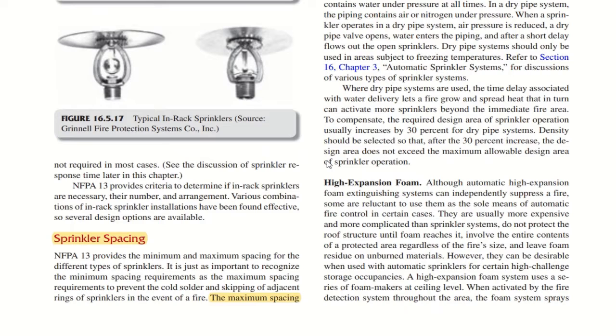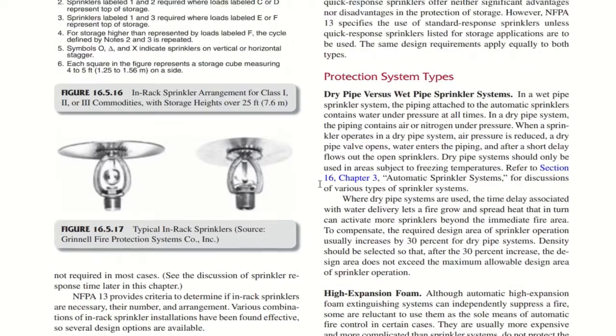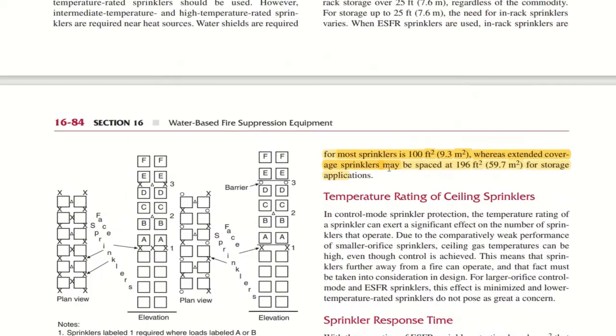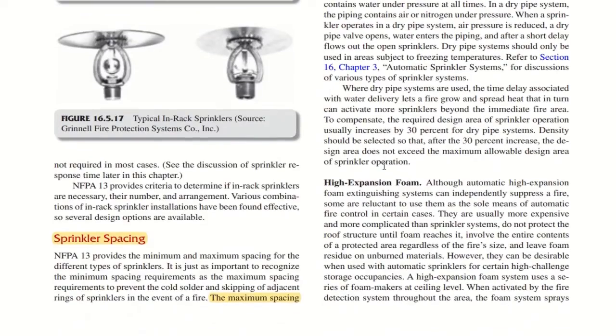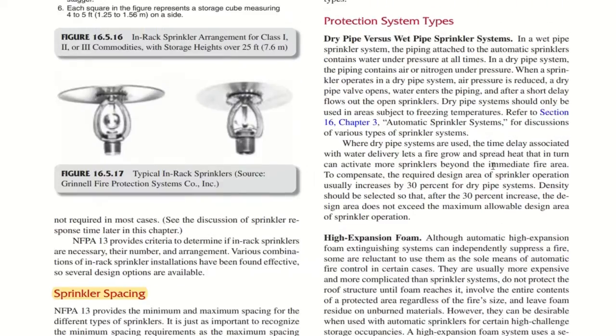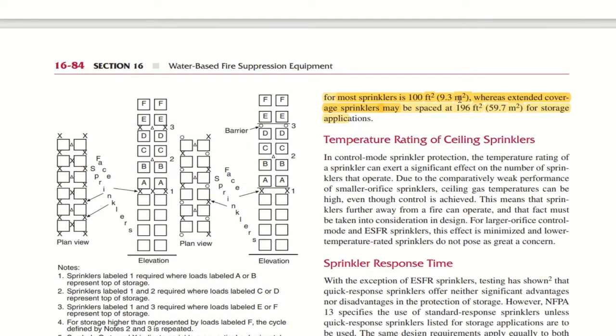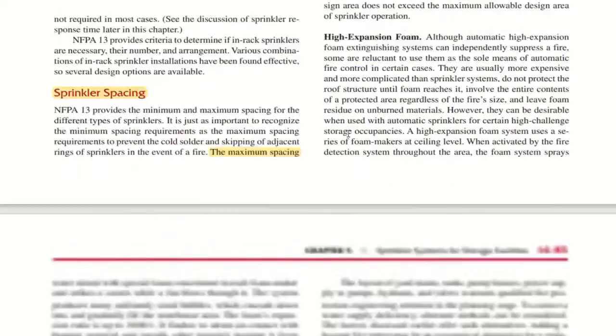So no need to remember anything. Since this is an open book exam, you should just have an idea where to find those topics in this fire protection handbook. This is the most important point. Sprinkler spacings are also mentioned. For storage applications, the maximum spacing for most sprinklers is 9.3 square meter, whereas extended coverage sprinklers may be spaced at 59.7 square meter for storage applications.